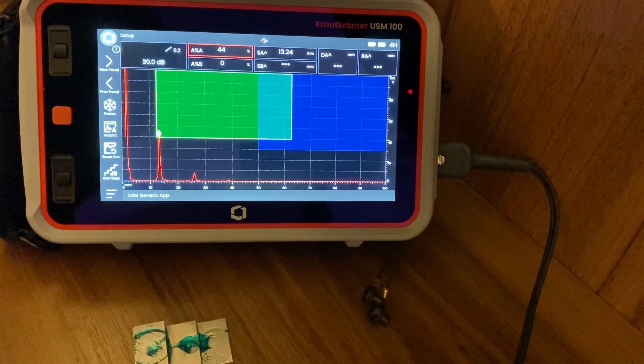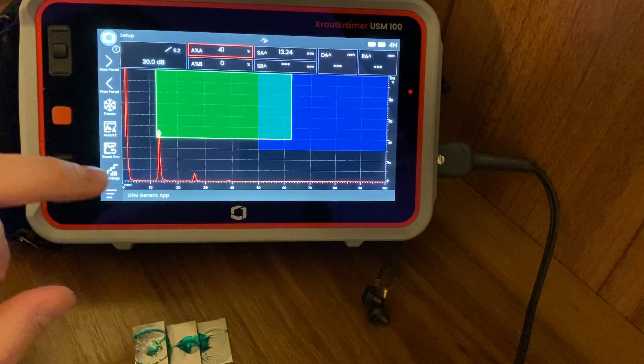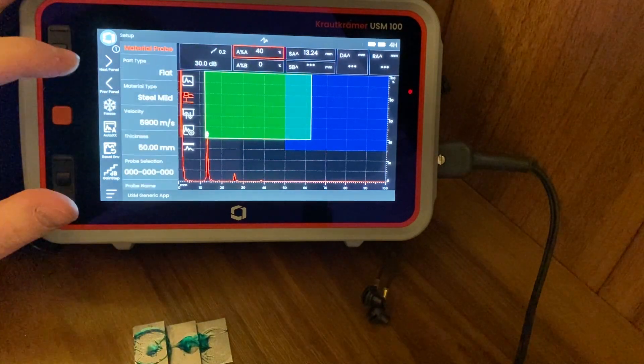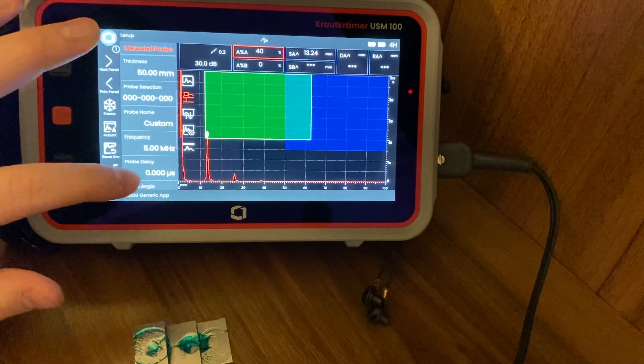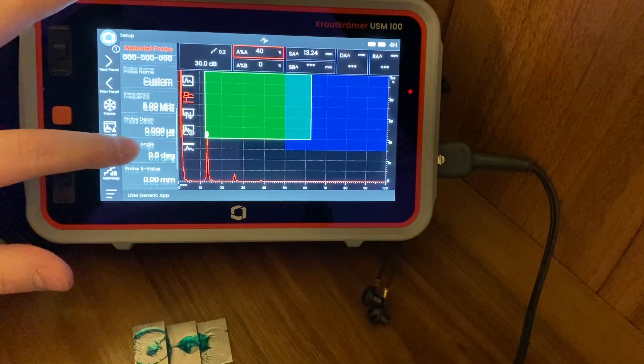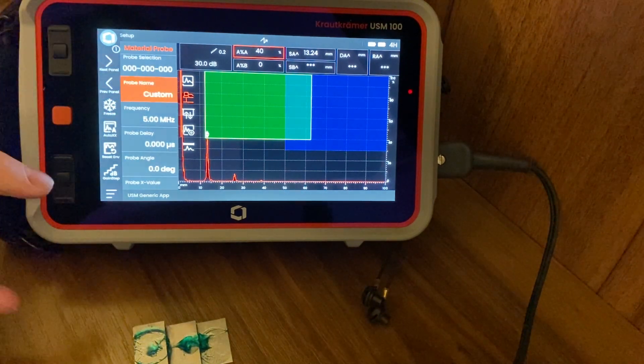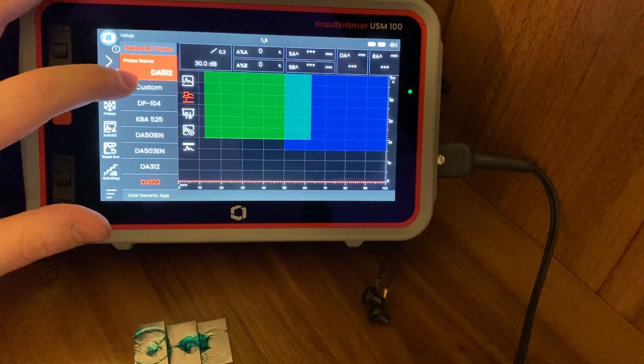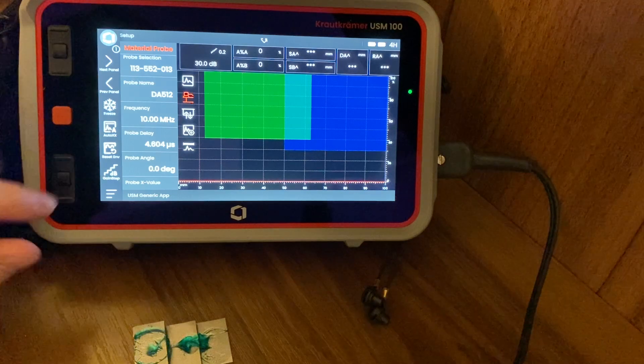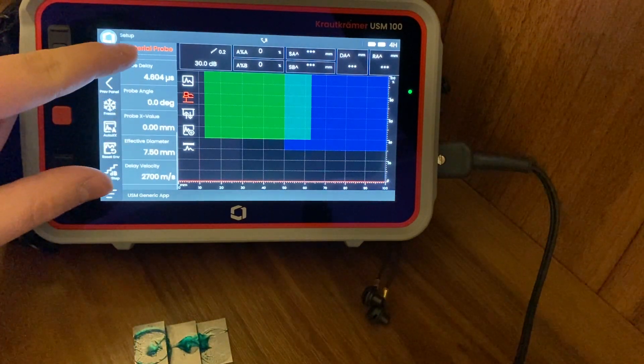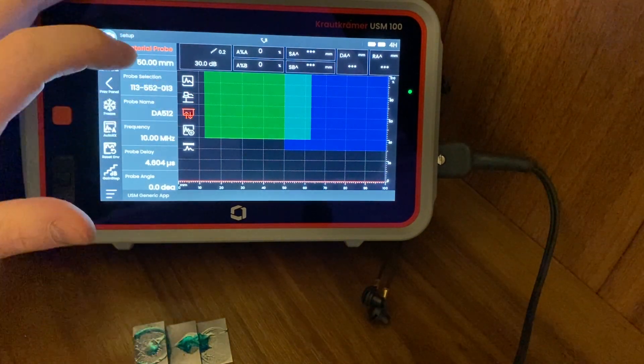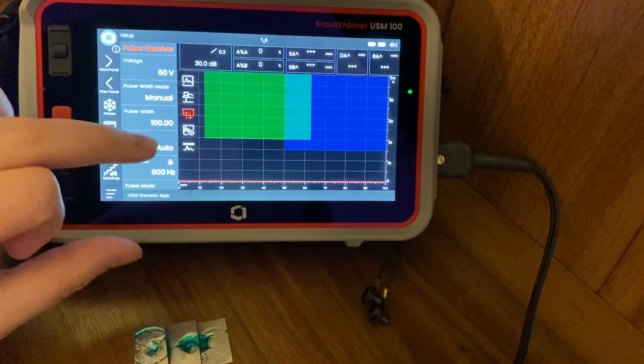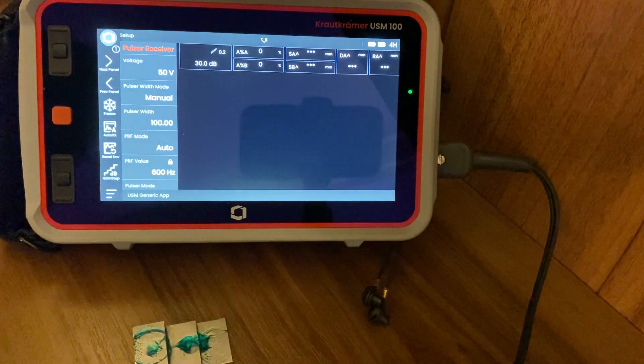At the very start, you see a panel here called Setup. All you really do here for the moment is go in and tell the probe you're using. I could manually input the frequency, the probe delay, probe angle, and everything here if I wanted, but that's so much work. So what I'm going to do is just tell it that I'm using a DA512 probe - it inputs all the parameters. It puts in delay, puts in the frequency, puts in the effective diameter, gives you everything. Outside of that, we could change things on display range, pulse, or receiver, moving the gates, but we don't need to worry about that.